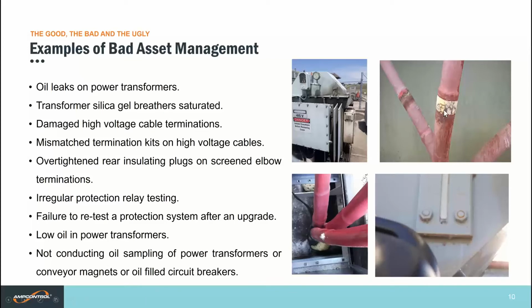That's an extreme condition, and it was caused by very high humidity in the location where it was. The bottom left photo, again, is where there is a lack of clearance between your phases, and you can see corona that's been produced on that cable. The last one there is indicating a low oil level in a sight glass on a transformer. That photo came from a site where the transformer was used to supply pumps. What was happening there was that during cold days, the oil level would drop, would drain out of the Buchholz protection relay and cause the transformer to trip. All that was needed there, once we found out that's what it was, was basically a top up of the oil.